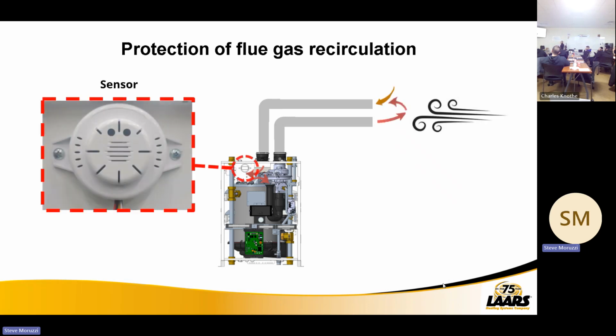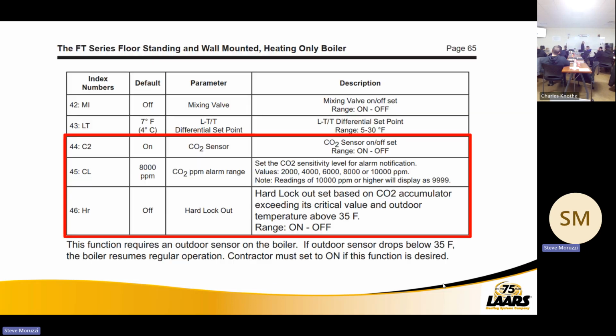So again, it's going to protect against flue gas recirculation, be that 20% of the time, is it 80% of the time? We'll talk about those settings. Okay, you can adjust that in the field. And that will potentially lock the boiler out depending on how you want to control it.